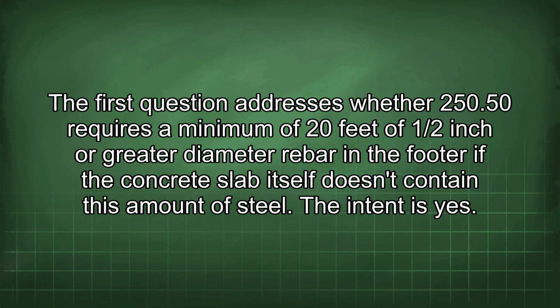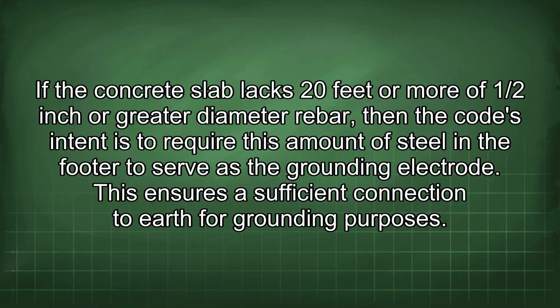The first question addresses whether 250.50 requires a minimum of 20 feet of 1/2 inch or greater diameter rebar in the footer if the concrete slab itself doesn't contain this amount of steel. The intent is yes. If the concrete slab lacks 20 feet or more of 1/2 inch or greater diameter rebar, then the code's intent is to require this amount of steel in the footer to serve as the grounding electrode. This ensures a sufficient connection to earth for grounding purposes.